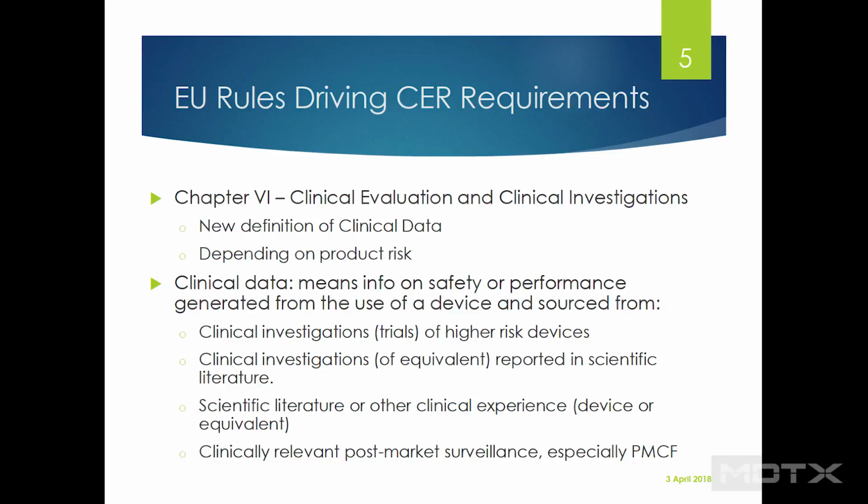There's also a new definition of clinical data, and that's an important one. It now means information on safety and performance generated from the use of the device. It's sourced from clinical investigations, which are trials, and trials are strictly for higher-risk devices. I'll talk about this again on another slide, but that means Class 3 devices, especially implantables.